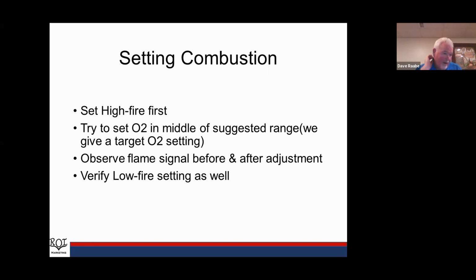So I wanted to talk a little bit about setting up combustion. Whenever we work on combustion, we want to set high fire first. So we want to turn on all the heating zones, the indirect, whatever, ramp it up to high fire. We give you a range and a target. So the target's pretty much in the middle of the range. I always try to set my O2 right in the middle of that range. So I'm going to do high fire first. And I should look at my flame signal before and after I make an adjustment, see, did that flame signal change at all? And then I want to go down to low fire and verify my low fire setting as well.